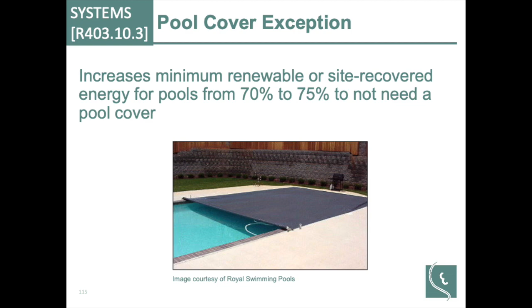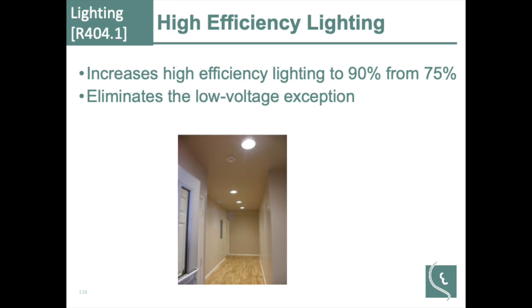High efficacy lighting is probably one of the biggest changes for the 2018 code for residential. We increased from 75% to 90% of installed luminaires having to be high efficacy. Illinois has an amendment on what counts as high efficacy, but basically use LED and you're generally fine. The big change is the low voltage exception is gone, so all those little MR16s now count in the 2018 code, which is part of why track lighting load calculations have changed.